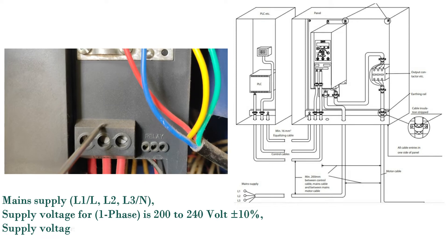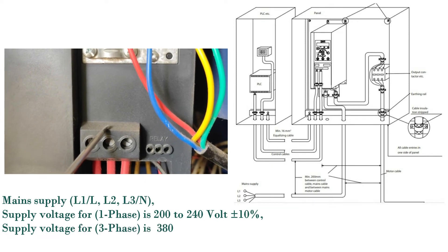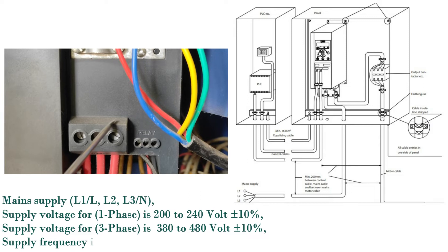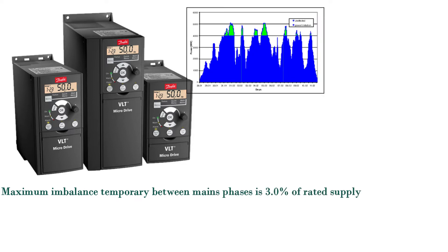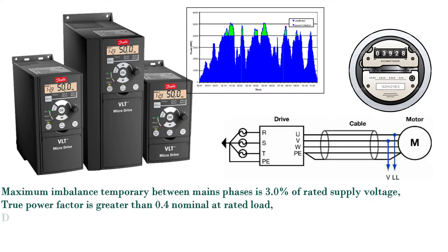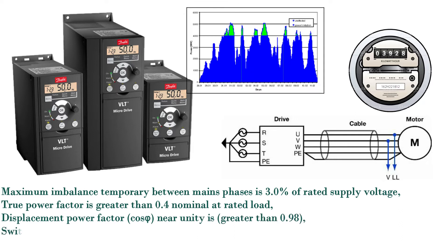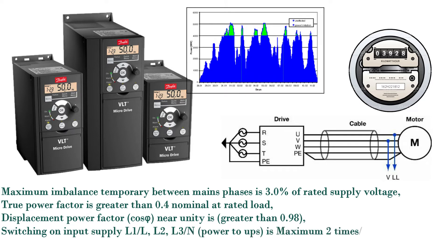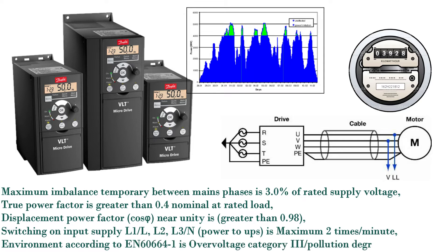Supply voltage is ±10%. Supply frequency is 50 or 60 Hz. Maximum imbalance temporary between mains phases is 3.0% of rated supply voltage. True power factor is greater than 0.4 nominal at rated load. Displacement power factor (cos φ) near unity is greater than 0.98. Switching on input supply L1-L, L2, L3-N is maximum 2 times per minute.